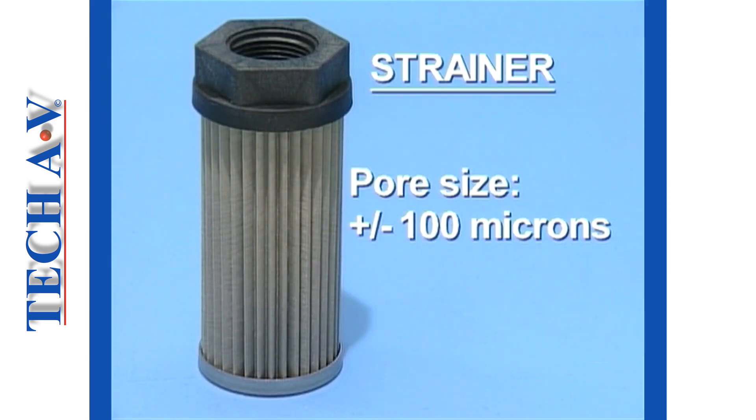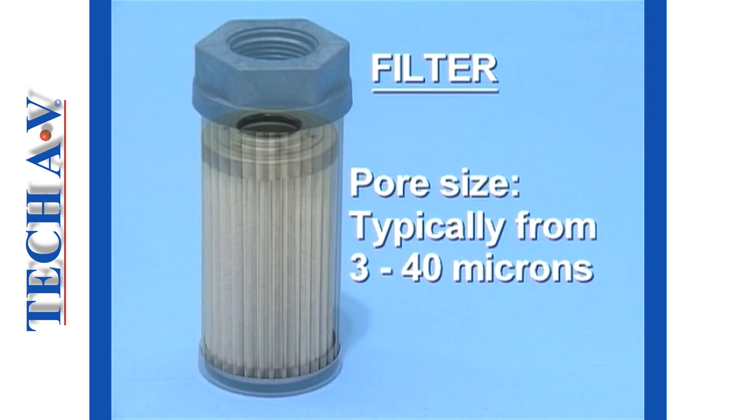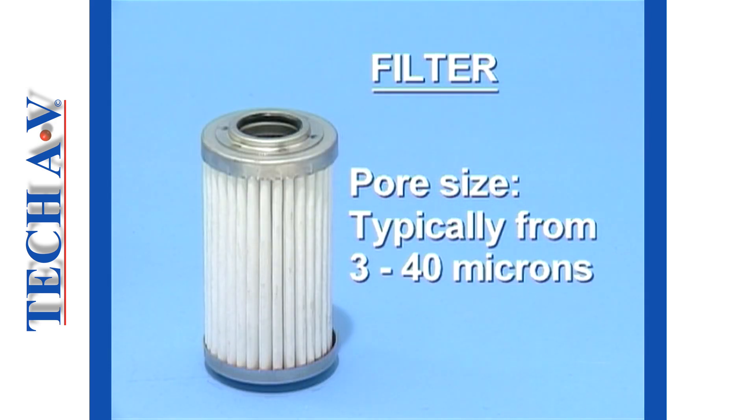A strainer is designed to trap relatively large particles. The average pore size of a strainer is around 100 microns. A filter is designed to trap smaller particles, often as small as 3 microns.